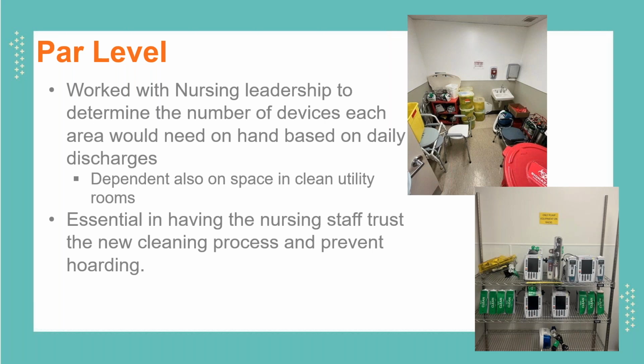Luckily, we have a real-time location system at our hospital. So that allows us to monitor how many devices are in each room without going there. So that helped us a lot. It is separate from the one that's used in the pumps. Correct. So we attach the tags, and we will see the tags. There is an infrared emitter in each clean and soiled utility room with a specific identifier. The tags read that signal and send it over via Wi-Fi or via a proprietary network to our server, and from any workstation, anybody can look where the pumps are.